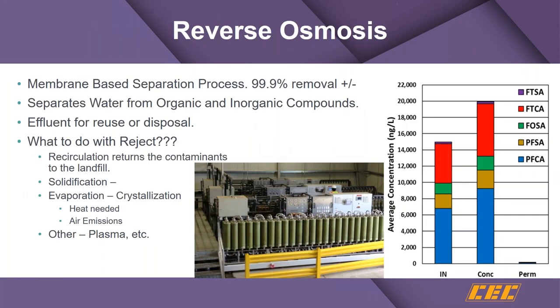Reverse osmosis is a very well-used technology for contaminated groundwater, and we're using it at a number of landfill leachate sites we're designing. This is a membrane separation device that removes virtually all long and short chain PFAS constituents as well as VOCs and other contaminants. Typically 80 to 90% of the water comes out as permeate, with somewhere between 10 to 20% as a reject that would have to be managed.